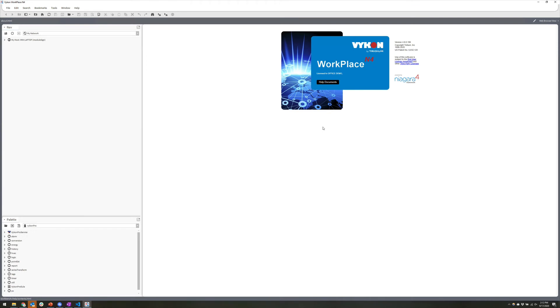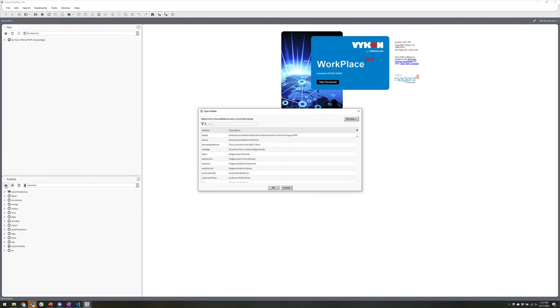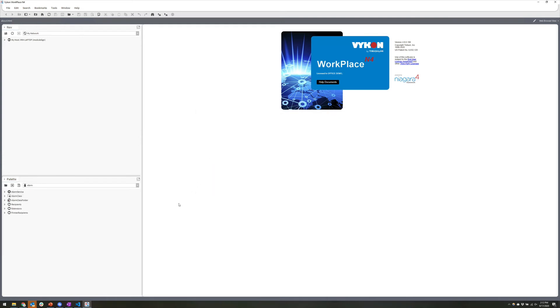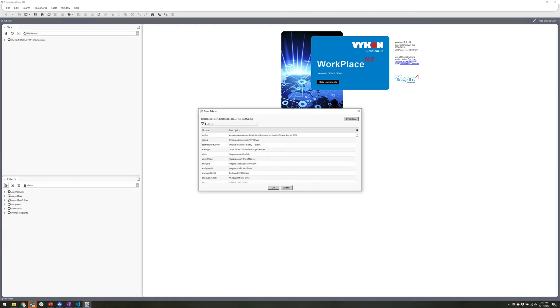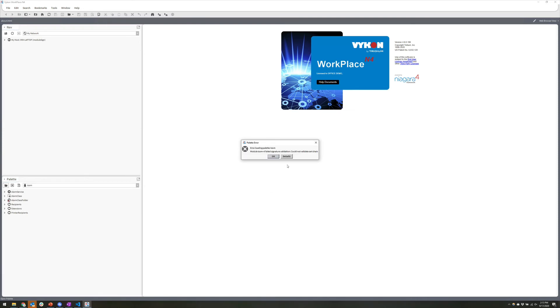I'm now open in Niagara 4.9. I can go over to my palette here as a demonstration and show you what module verification looks like in practice. If I pull up a random module — something like Alarm, which comes out of the box with your Niagara install — you can see it opens no problem at all. But I also have a TCOM module here from Maxline Solutions, which is an older version. It has no code signing in it at all, and when I open it up, you'll see an error message comes up.